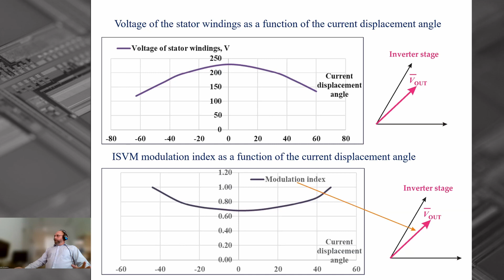To solve this problem, we need to change the modulation index of the inverter side and widen the modulation index manipulation zone. We need to change the connection of the motor: instead of connecting in star, we connect the motor in delta, which makes a wider range for modulation index manipulation.